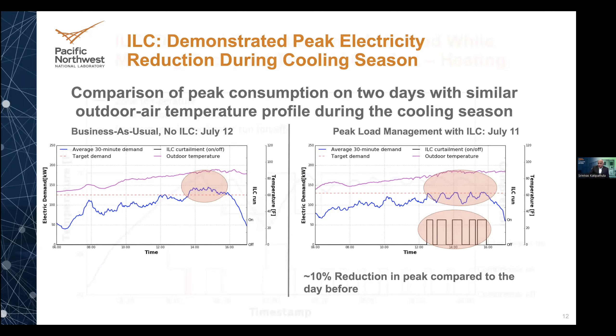that bubble there. When we were managing the peak on July 11th, several times between 1 and 4 p.m., the electricity consumption reached the target value of 130 kW. And each time there were some heat pumps that were curtailed to manage that. In this case, compared to the first day, the reduction was about 10%. Curtailing heat pumps or any distributed energy resources is one thing, or half the solution. We also have to look at the service levels. So in the next slide, I'm going to show you that.